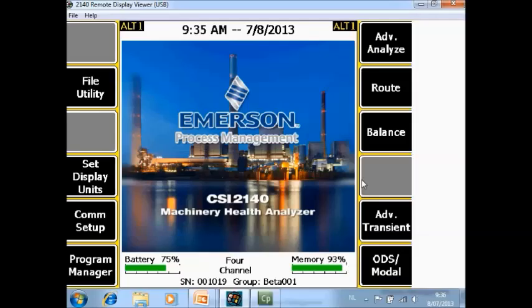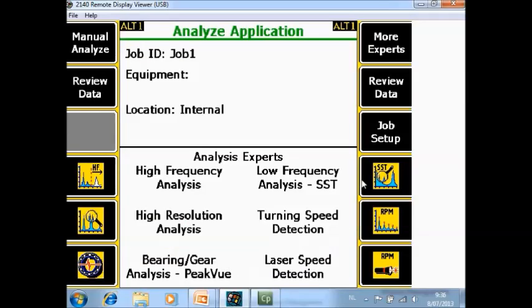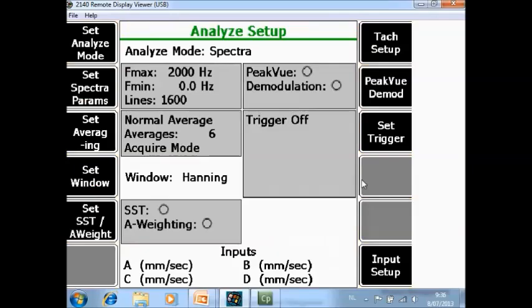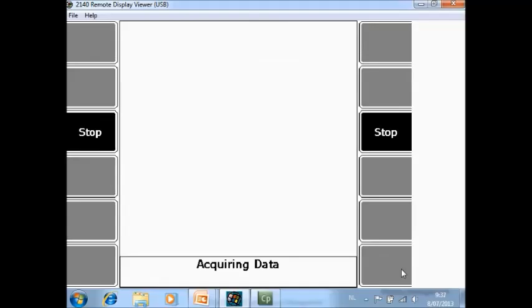On the home screen of the analyzer go to F7 Advanced Analyze, go to F1 Manual Analyze, and as you can see here I will measure from 0 to 2000 Hz 1600 lines with 6 averages on 4 channels. I will start a machine now, and I will collect data.